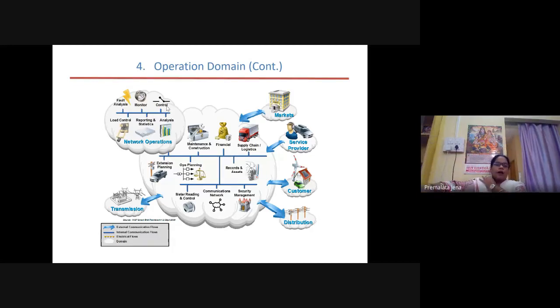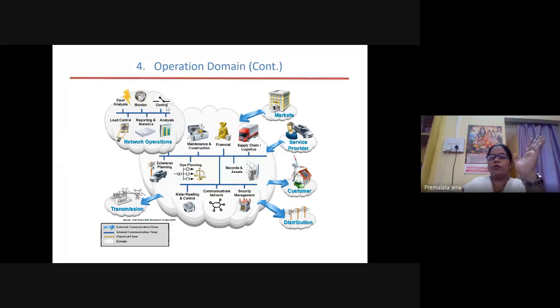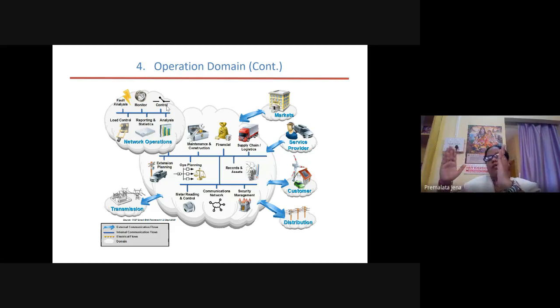But in a smart grid environment, even though I have the capacitor bank, I keep a switch in series with it made of IGBTs or some electronic soft switch—we call it a soft transfer switch. This means it can transfer from on mode to off mode. By giving a signal to the gate drive circuit of the IGBT, it will switch on at one time and off at another. So a number of capacitor banks get connected in parallel, and my voltage profile gets controlled accordingly.